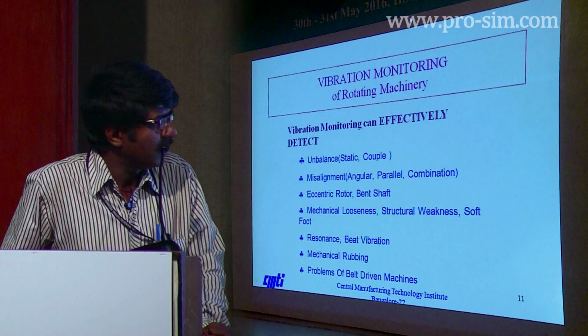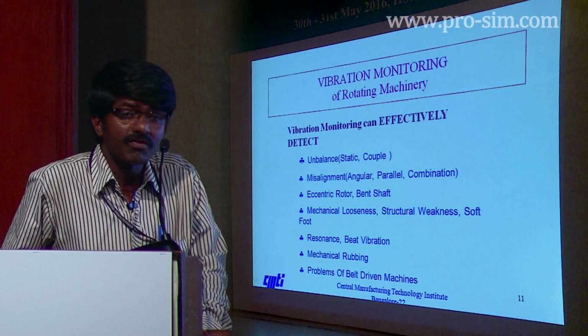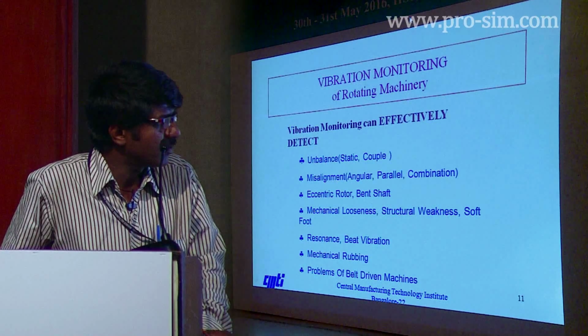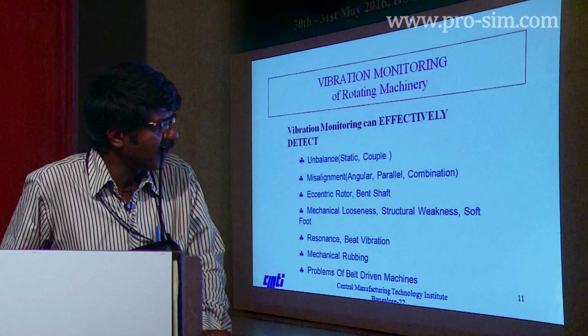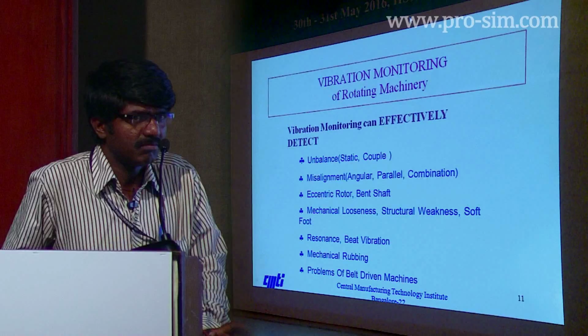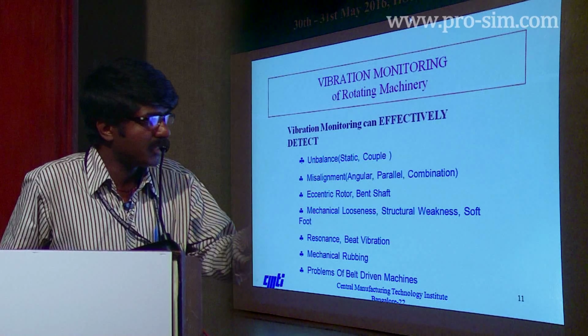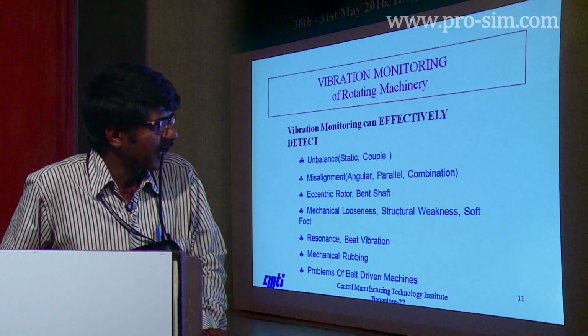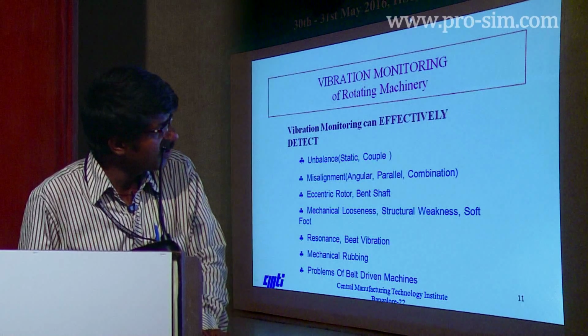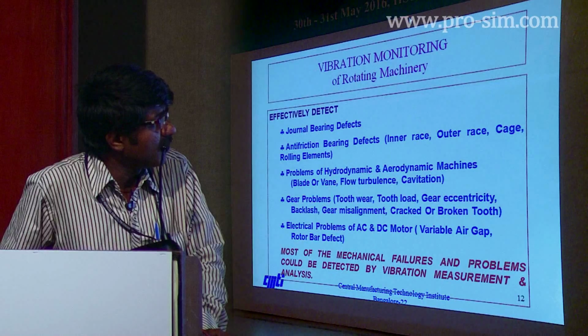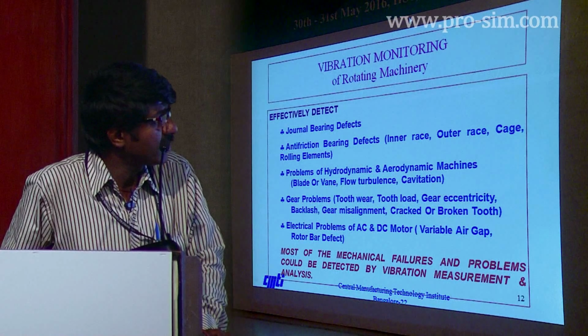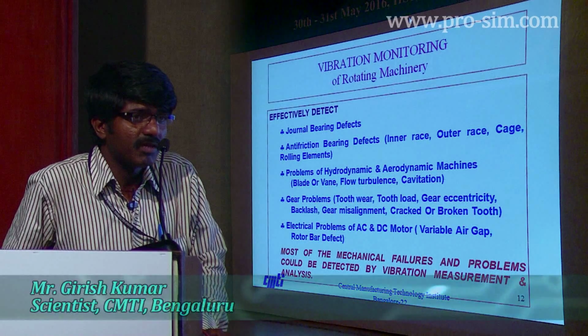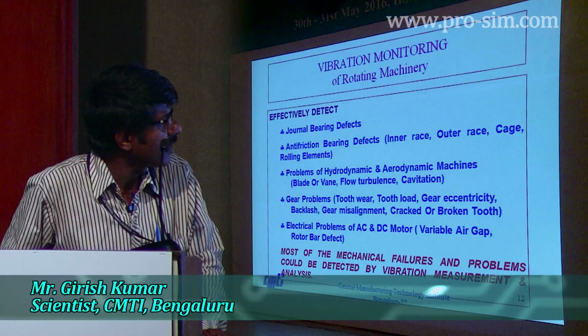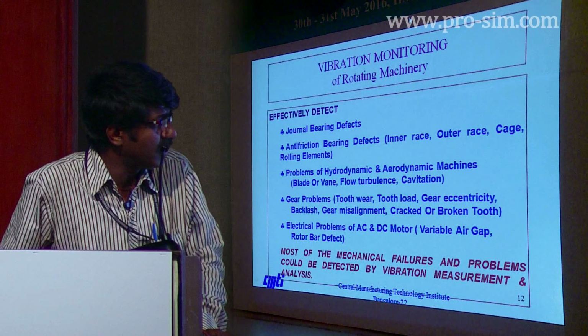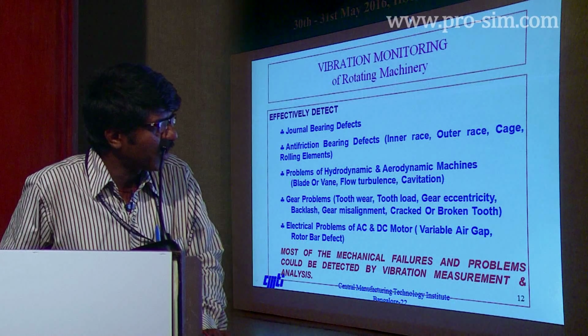Eccentric rotor, bent shaft, mechanical looseness, even structural weakness, soft foot if the machine is not mounted properly, and resonance, which is one of the very important phenomena. Beat vibration occurs if two machines are running very close to each other at almost the same speed, with a difference of maybe 1 or 2 hertz. Also mechanical rubbing and problems of belt driven machines. We can also find out journal bearing defects and anti-friction bearing defects. By using vibration monitoring, we can pinpoint whether the inner race, outer race, cage, or even the ball has a problem. To that extent, we can use vibration monitoring. Also problems related to hydrodynamic and aerodynamic machines, gear problems, and electrical problems of AC/DC motors.